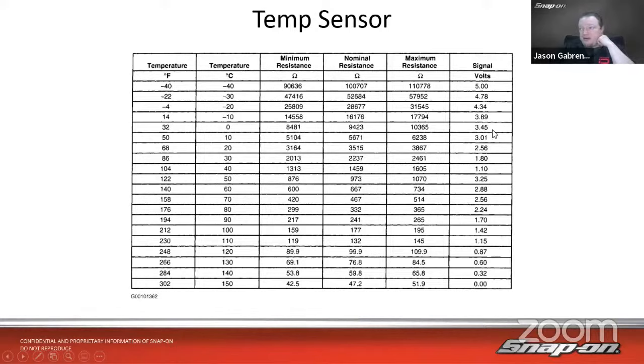So that would mean, in this case, maybe it's reading down in this range. So if I'm only reading voltage and not reading temperature, I could be testing this and think it's reading incorrectly if I didn't know that it switches voltage from a high resistance to a low resistance circuit somewhere around that 104 degree range. So if I didn't know that, that's why you always need to check your information and read your information to see, do I have a difference in resistance?